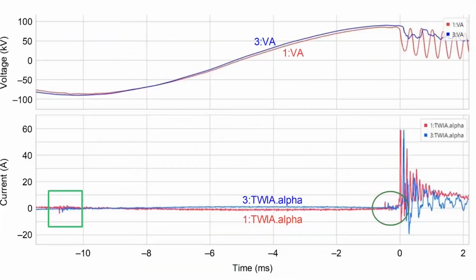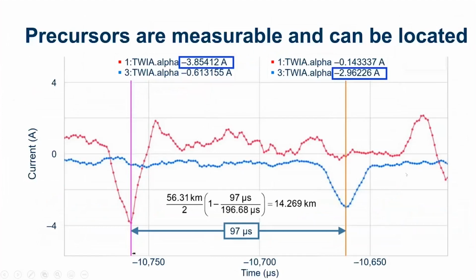if we look back, what we're looking at is these two precursors here. When the fault occurred, we could also look at the traveling wave fault location that was determined for the actual fault, and it was found to be pretty close to what we see here, about 14.3 kilometers. So these precursor waves were able to accurately identify the fault location before the fault actually occurred. And this feature is available on the T400L and the new T401L.